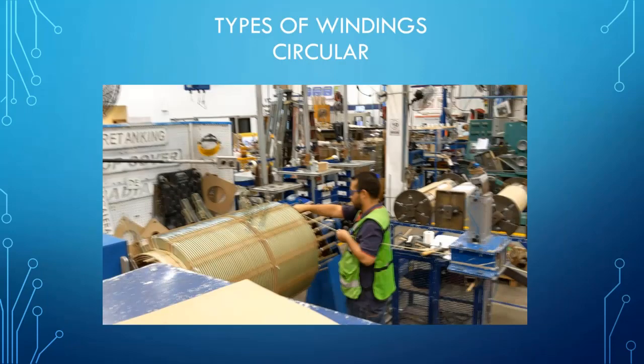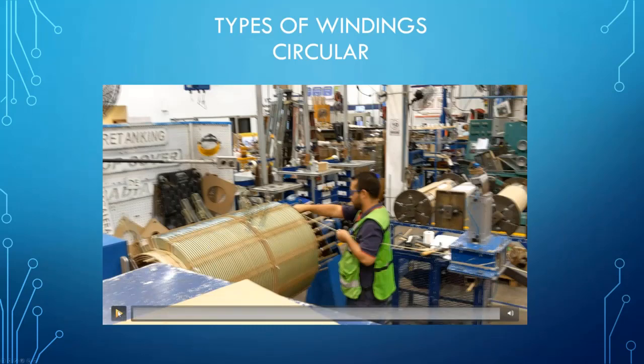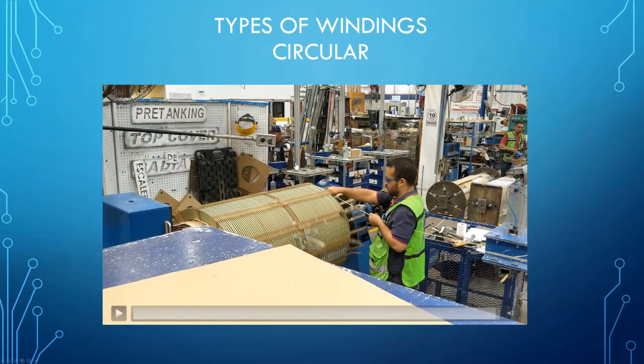So here is a circular winding. Let's see if this video will work. So hopefully everybody could see that video, and obviously it's of a gentleman winding a circular type winding, and this transformer is probably, judging by the size of it, maybe a 12, 15, could be 18, 20 MVA transformer. And certainly circular windings are superior. In fact, they're used exclusively when you get into power transformers, transformers above 10 or 12 MVA.